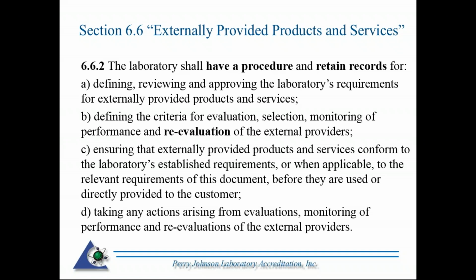C, ensuring that externally provided products and services conform to the laboratory's established requirements or, when applicable, to the relevant requirements of this document before they are used or directly provided to the customer. This document, of course, is 17025. So if, for example, you're complying with traceability requirements within the 17025 standard, your supplier must comply with those requirements. If you have specific requirements as stated in your own internal quality management system, you want to assure that any supplier of any product or service will comply.